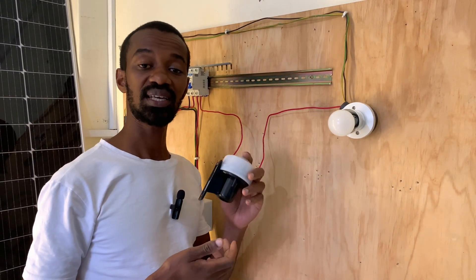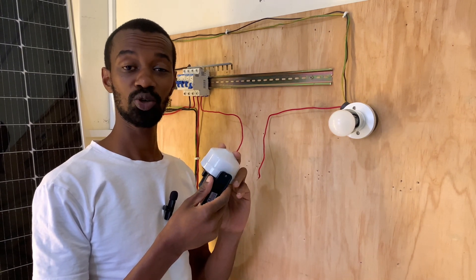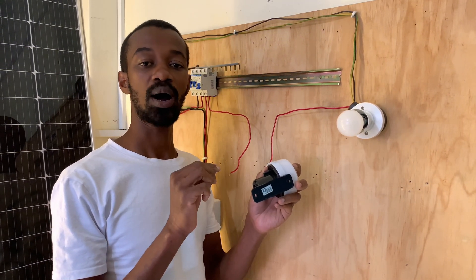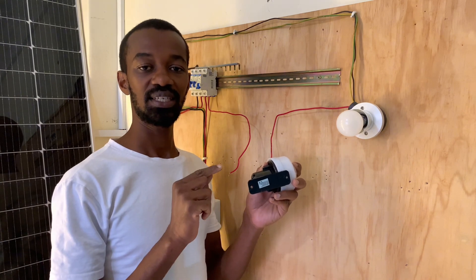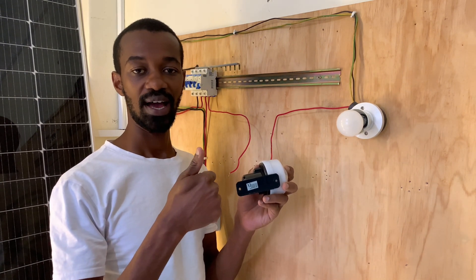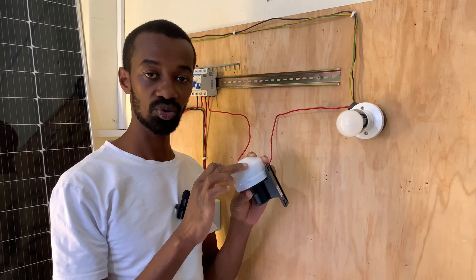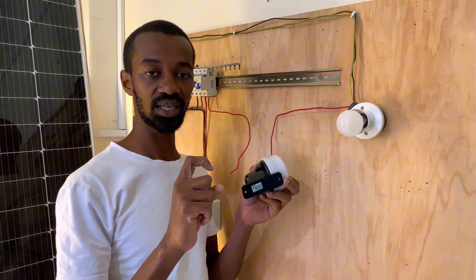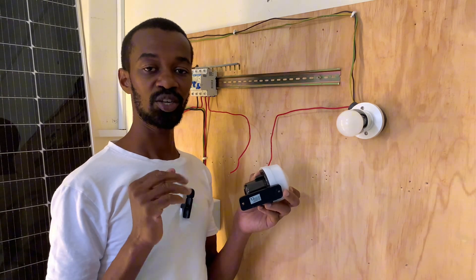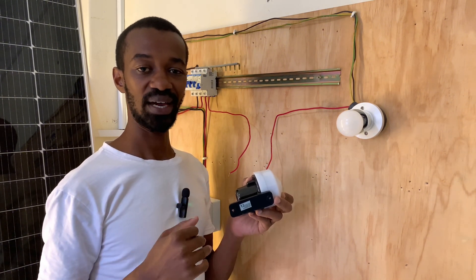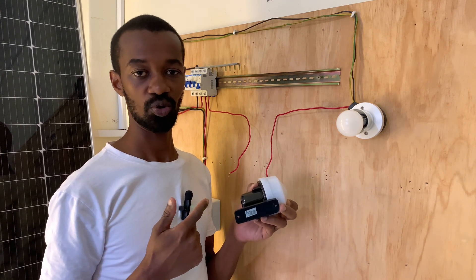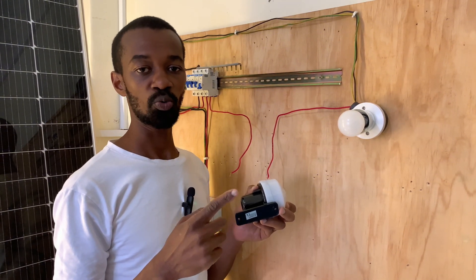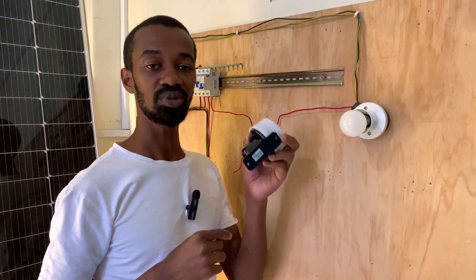For us to understand this photo cell wiring, it is important to mention two important things. This photo cell must receive a power supply — first it has a connection for the live, and then the neutral, which is a return, because the circuit in here has to be fed for it to operate. Then there is an output signal, which is also a live and a neutral. The neutral is shared between incoming and outgoing, so we will just have one neutral connection. For the live out, that is one separate connection — so we will need to wire three cables to this photo cell.